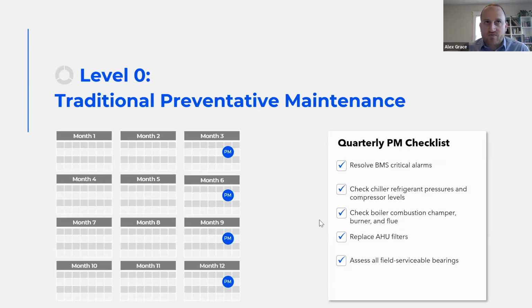To go a little deeper: at level zero, we've got a traditional PM program. Once a quarter, we check alarms, maybe check chiller refrigerant pressures, compressor levels on the boilers, look at combustion chambers, burners, flues, replace filters, grease bearings, you name it. All the standard preventative maintenance items happening on a time-based schedule.